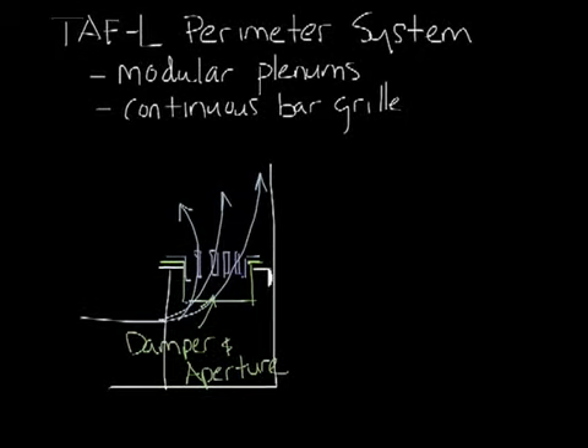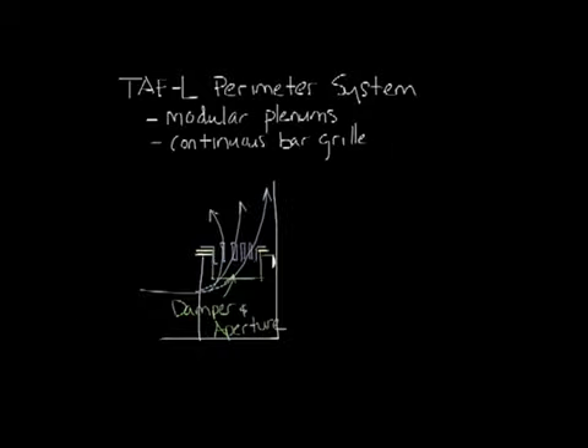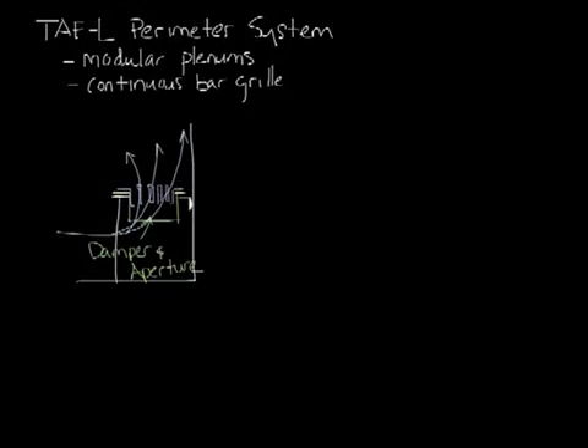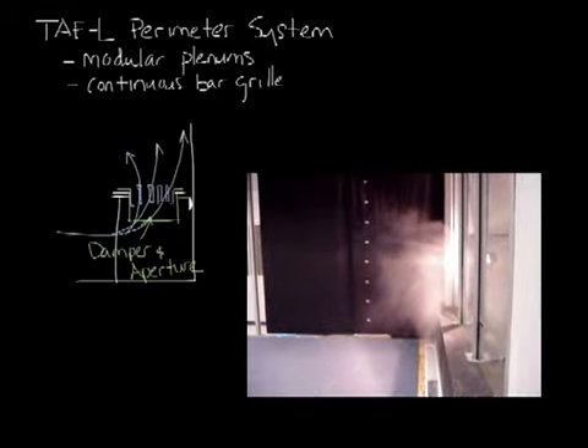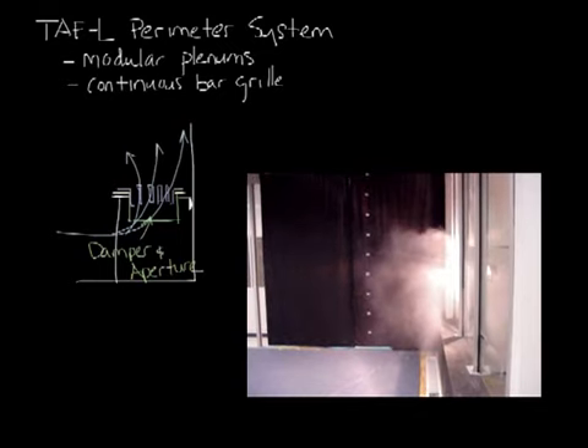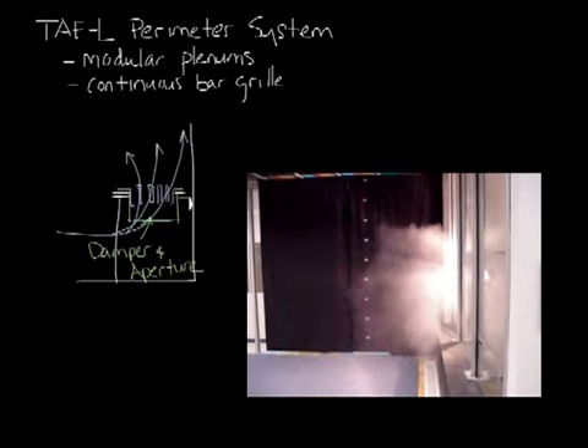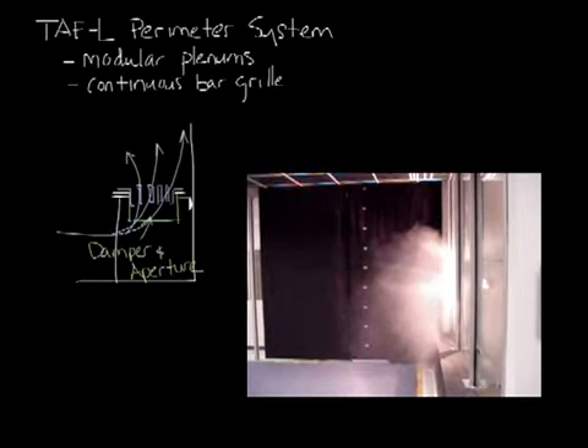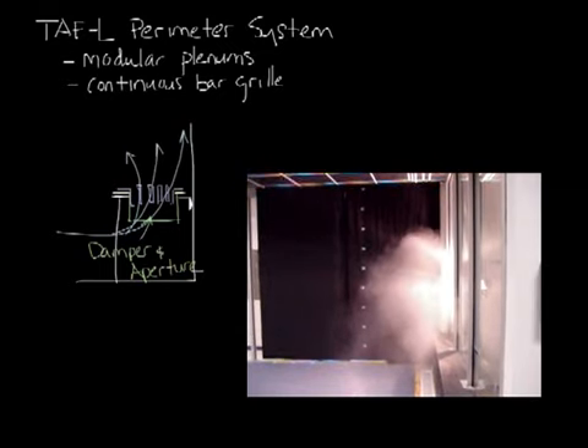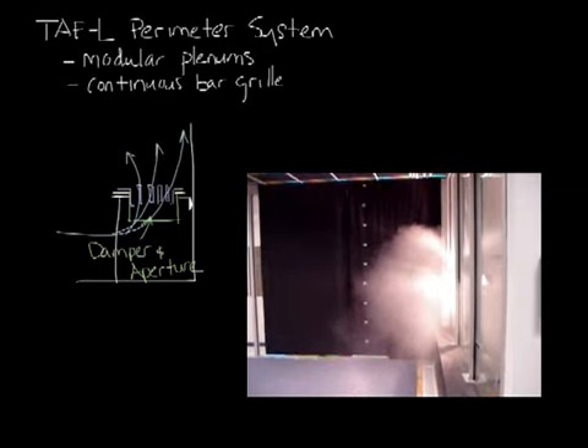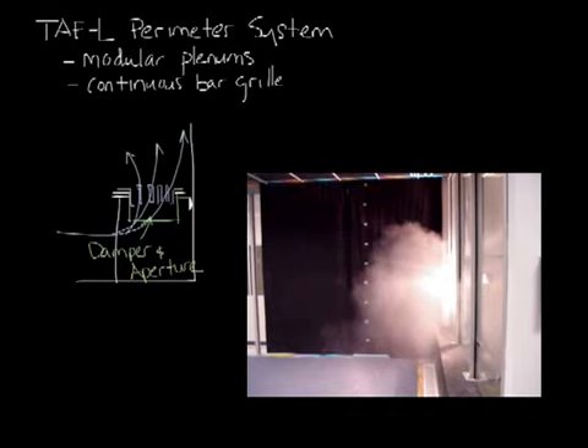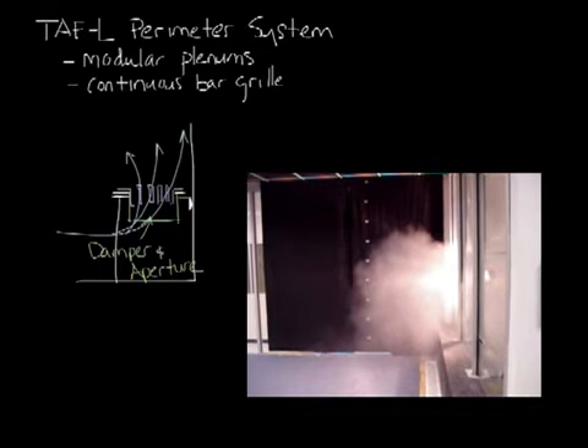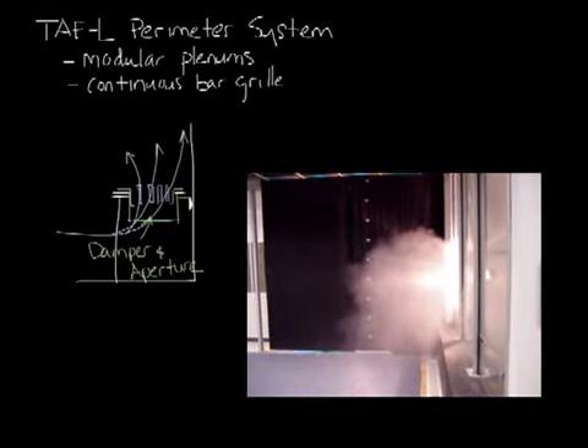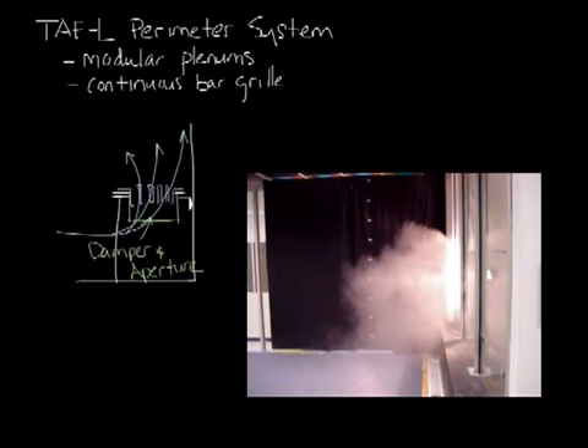Let me move this out of the way a little bit now so I can show you a video of it in action. Okay, let me bring the video in, and we'll put it right here. So what you see here is our cold wall and our raised floor. The air is coming out of the raised floor, and it's enough airflow to handle the cold wall. I think this is about 225 CFM in a 4-foot section. And you can see that although it's using a linear bar grill, it has a fairly short throw.